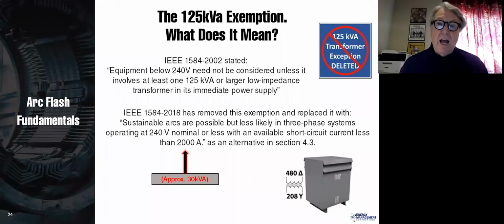Well, in 2018, IEEE came out with a newer version of that standard, and they decided to remove the exemption. And they replaced that with sustainable arcs are possible, but less likely in three-phase systems operating at 240 volts nominal or less with an available short circuit current less than 2,000 amps. Well, what does that mean? Possible, but less likely? Basically, it means that there is no exemption. Doesn't matter. Regardless of what transformer size is there, you have to do the full study. So if you were using that 125 kVA exemption, it's gone.